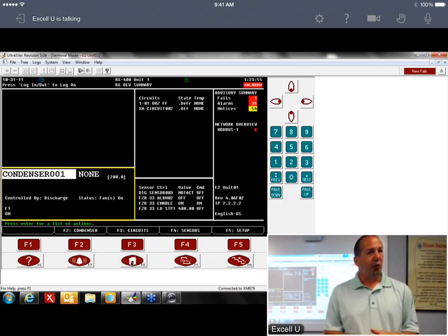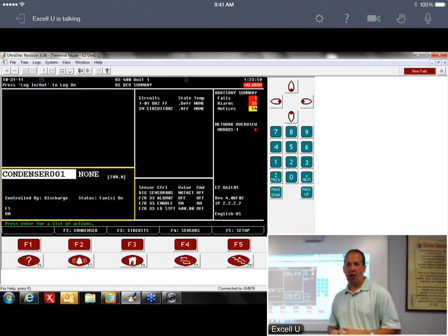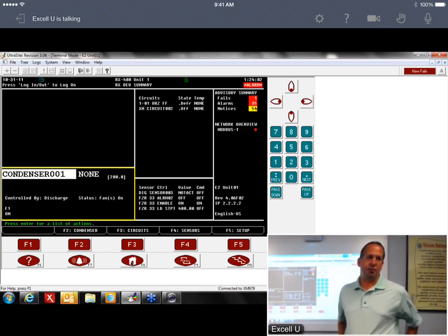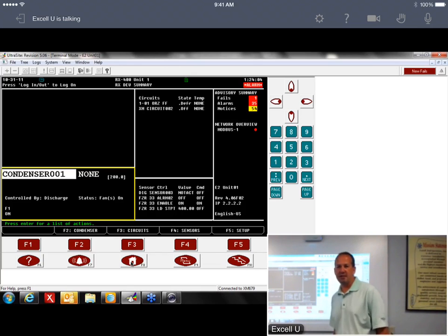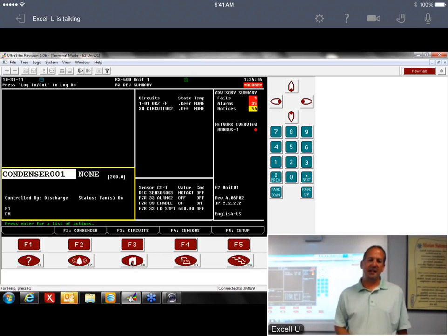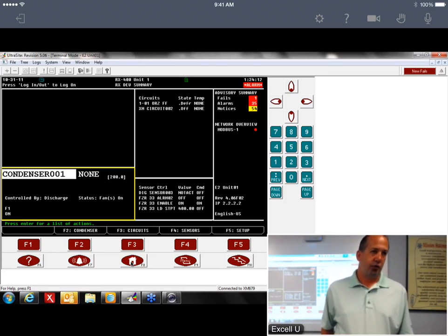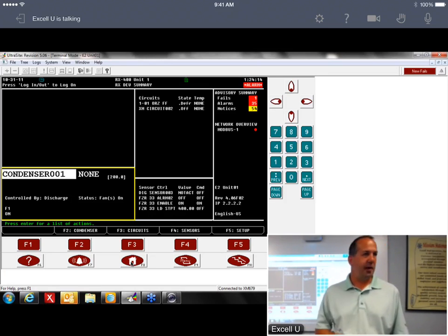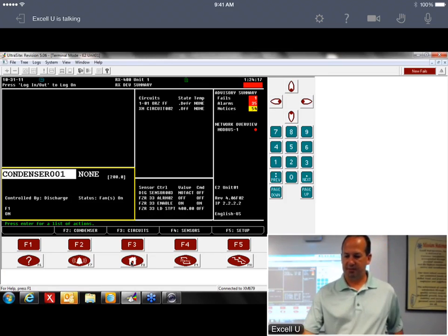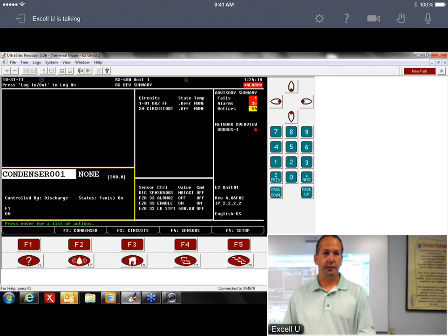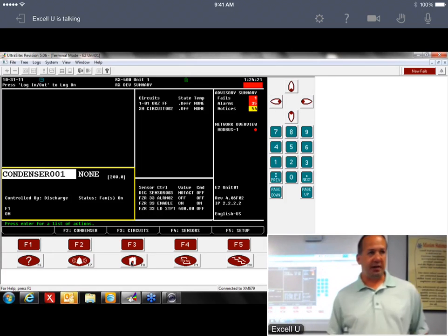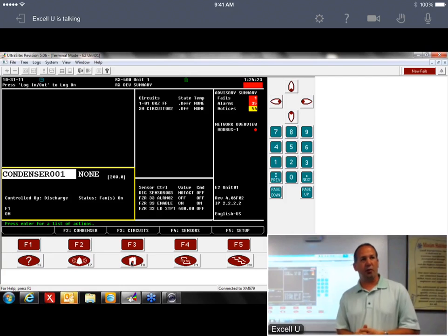One of the good things with the adaptive algorithm is you don't have to mess with P and ID settings. You can spend weeks chasing your tail with P and ID settings, but this thing learns itself, so you don't have to mess with those. So we don't have to put the 0.5, 0.5? Correct, you don't have to mess with any of those. So there's no throttle on these because it's all controlled by superheat, all part of this adaptive algorithm.